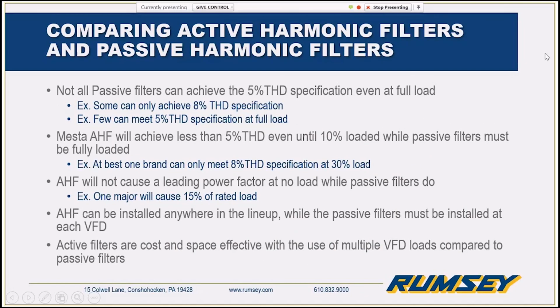Passive filters, just to keep in mind, not all passive filters are designed to meet that 5% specification. Always want to check into that depending on which band you're falling into. Great tools to meet that 8% spec. The one that we recommend most if you're trying to meet 5% is MTE, which is another Rockwell Encompass product partner. They have a great adaptive passive filter, they call it ADP, that is designed to try to meet that 5% specification. And they can handle being lightly loaded better than many other brands. But that's something an active filter doesn't have the same kind of problem with as passive filters. We can be extremely lightly loaded.